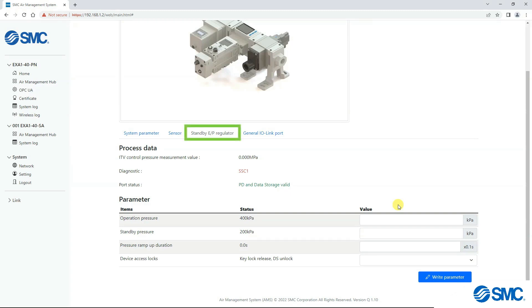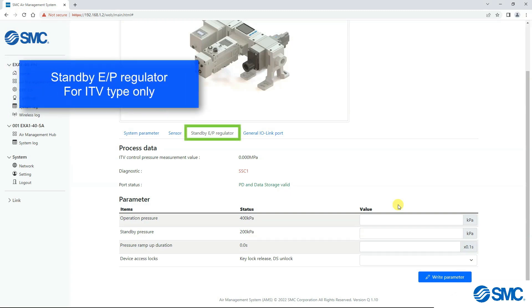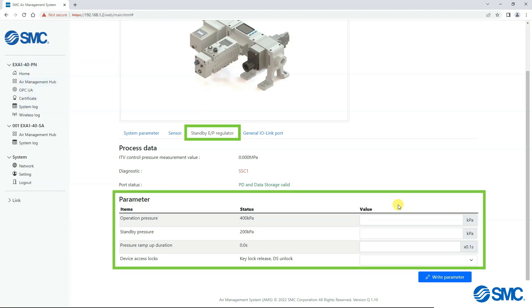The Standby EP Regulator tab will appear for systems that are ITV type only. Here we can set the operating and standby pressures, we can also set the pressure ramp up duration. There is also an option to lock the device.